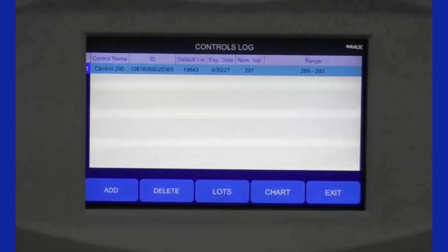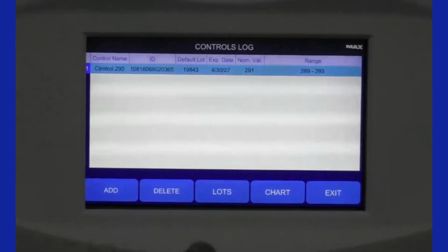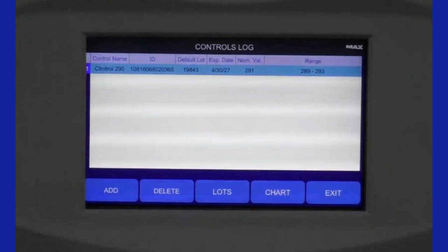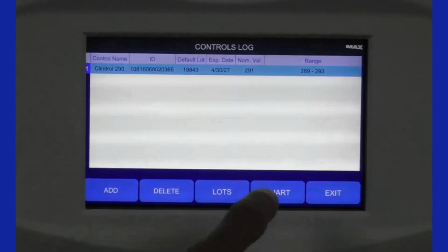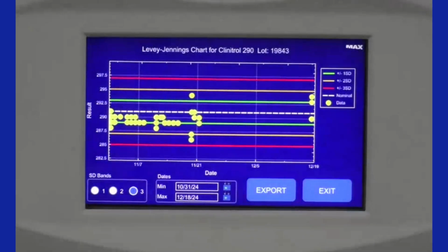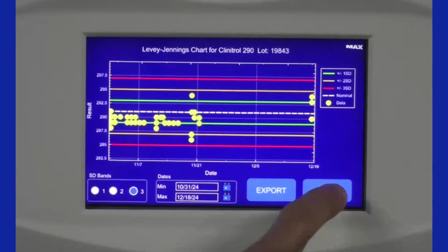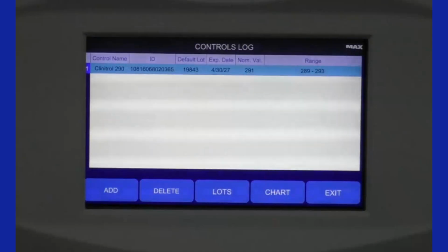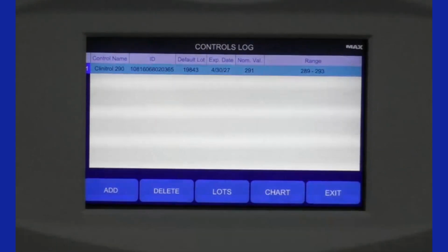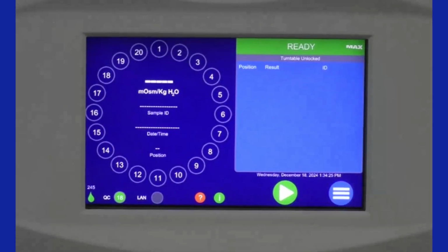Something else that's kind of cool you can do from this menu is you can chart a Levey-Jennings plot using this lot. So every single control that I've run under this lot, I can chart in this plot. And you can actually see within different levels of confidence based on those lines. So the red one is 3 SDs, the yellow 2, the green is 1, how your controls have performed over time. You can select a date range that you want to assess the performance of your controls within. You can also export this result as well. So pretty neat little feature on that one as well for each specific control lot.